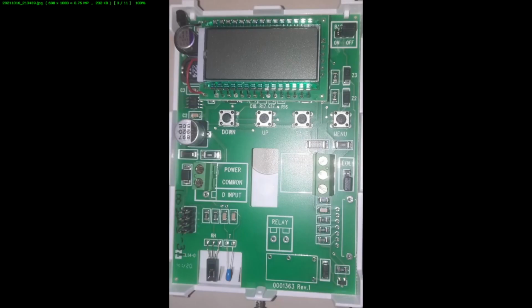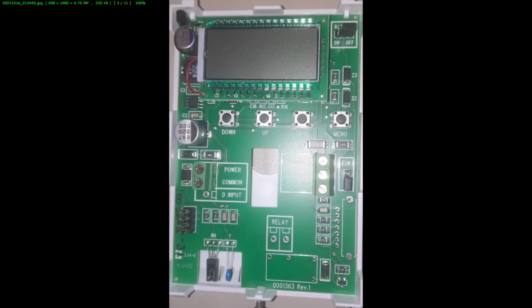And if we go back, you can see they have a power connection, and then it's sort of bleached out by the light, but there's the Modbus, the shield, and the plus and the negative connection here. If it is the last device on the daisy chain. You have to set the end of line jumper. In this case, this one was not, but if it was, you would put the jumper across both. You can also get them where this LCD is visible through the cover. I didn't choose to get that one. And if so, you can choose whether or not it's backlit or not. But otherwise, you can read the value of these sensors via the centralized software.